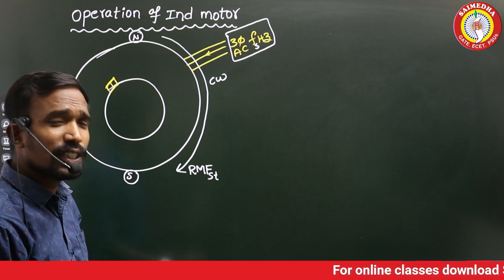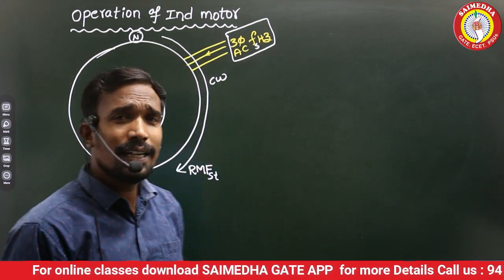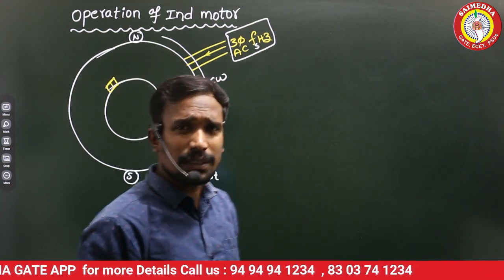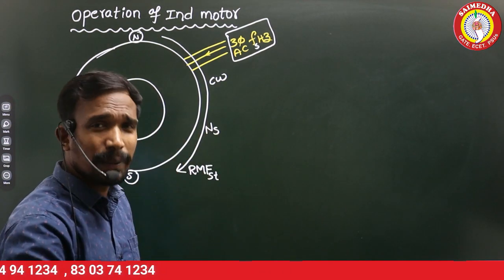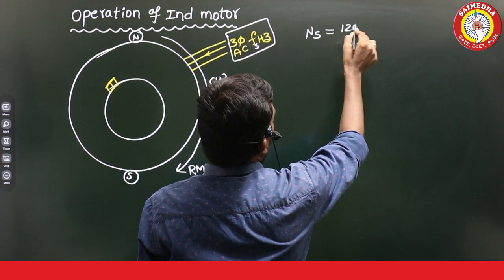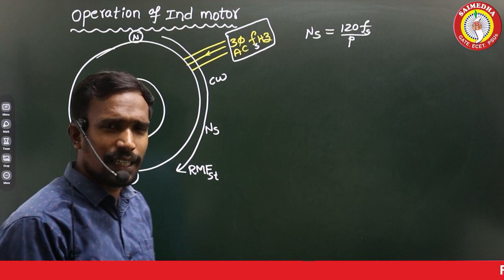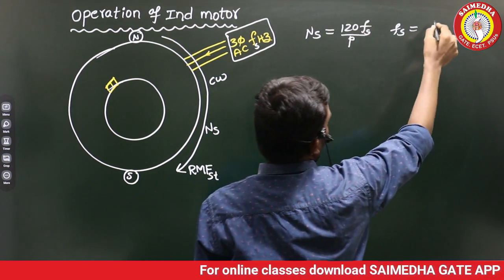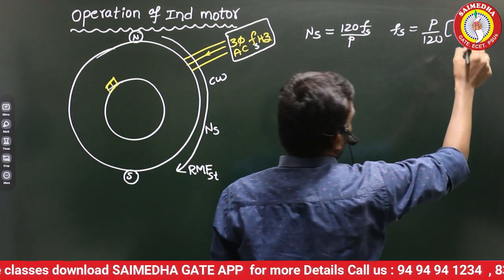When supply is given to the stator, the stator won't rotate — it is stationary. But in that stator, a magnetic field is created which rotates in the clockwise direction with some speed. That speed is called synchronous speed. The synchronous speed formula is: Ns = 120F / P, where F is the stator or supply frequency. To calculate supply frequency: Fs = (P / 120) × Ns.